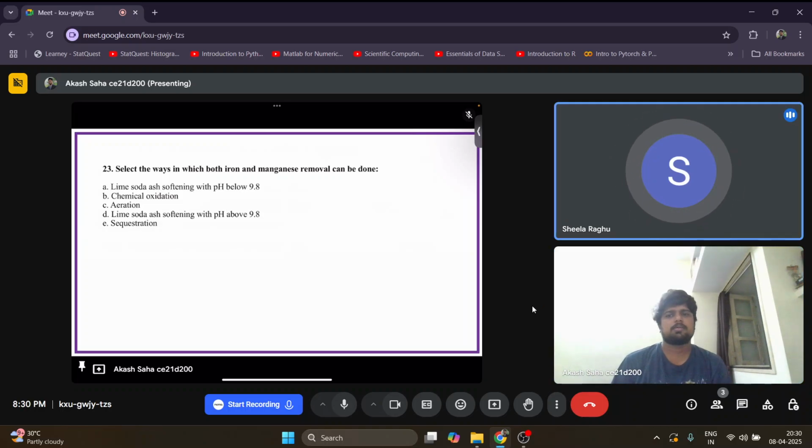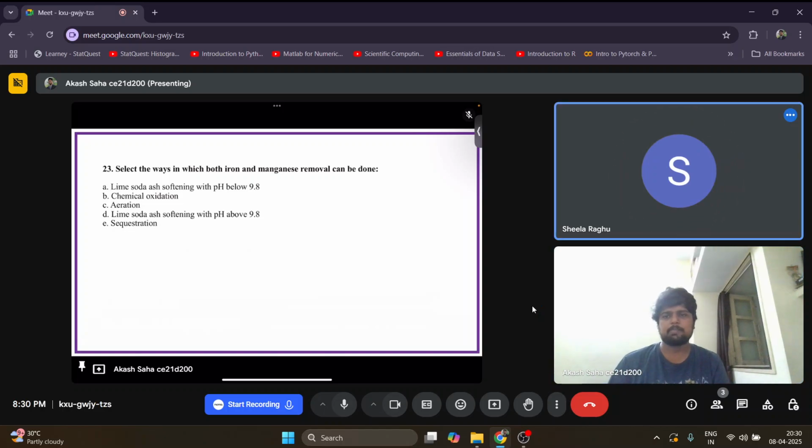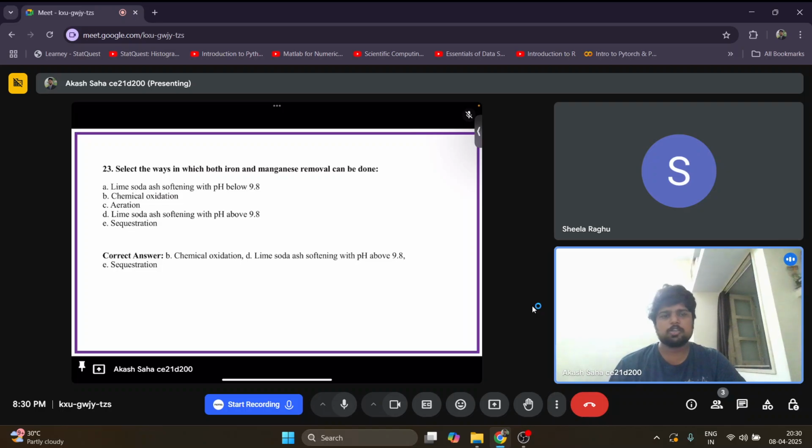Iron and manganese, yes, right. It can be removed by the lime soda method, but the pH should be more than 9.5. If it is less than 9.5, it will not get precipitated. Then chemical oxidation also we can use. If we can oxidize ferrous and manganese 2 plus to 3 plus or 4 plus forms, then we get it precipitated.